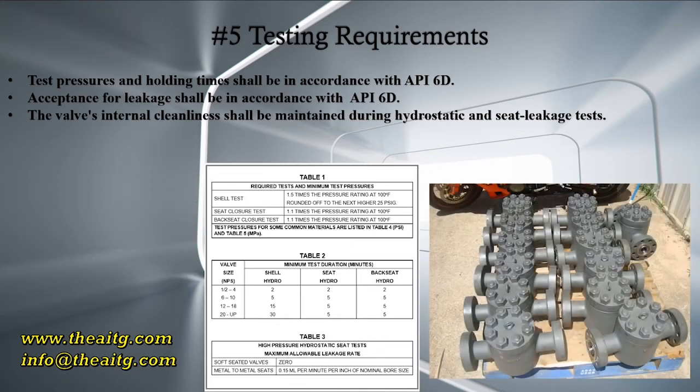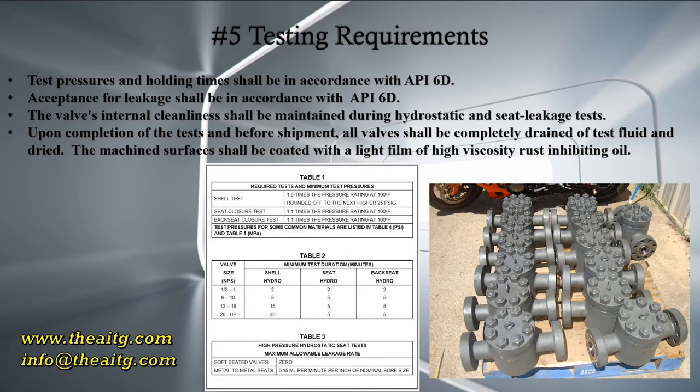Valves' internal cleanliness shall be maintained during hydrostatic tests and seat leakage tests. Upon completion of the test and before shipment, all valves shall be completely drained of test fluid and dried. Machine surfaces shall be coated with a light film of high viscosity rust inhibiting oil.